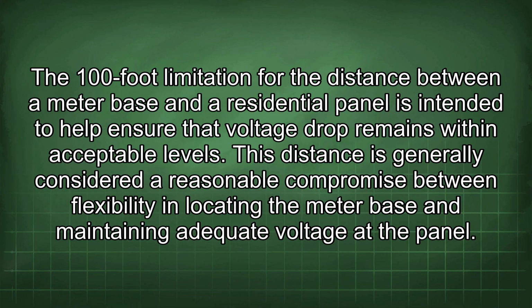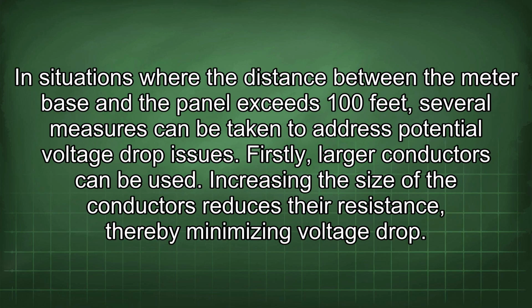The 100-foot limitation for the distance between a meter base and a residential panel is intended to help ensure the voltage drop remains within acceptable levels. This distance is generally considered a reasonable compromise between flexibility in locating the meter base and maintaining adequate voltage at the panel. In situations where the distance between the meter base and the panel exceeds 100 feet, several measures can be taken to address potential voltage drop issues.